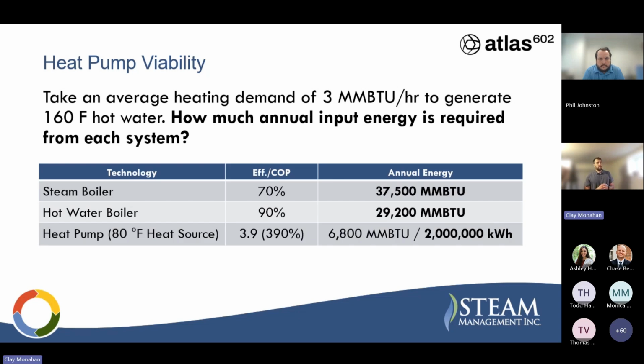So a steam boiler with that combined system efficiency of 70%, the annual energy to meet that demand at the end user would be something like 37,500 MMBTU. A hot water boiler might be able to do it at 29,200 MMBTU, and a heat pump at a 3.9 COP, using that same calculation with the 50% actual achievable COP efficiency factor applied, is going to yield 6,800 MMBTU, which is just an energy unit, just like kWh. So if we convert to kWh, it's about 2 million kWh. All right, so we have our different energy inputs, and just pausing a beat on this. If there's any questions on translating from one to the other, happy to field them. But they're both energy units, and you can convert from one to the other.